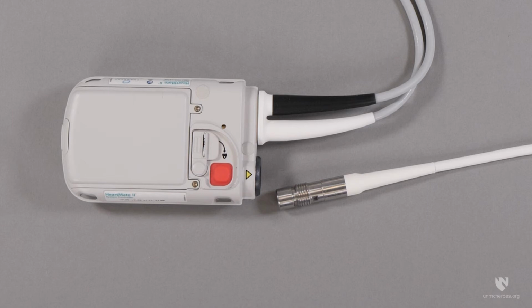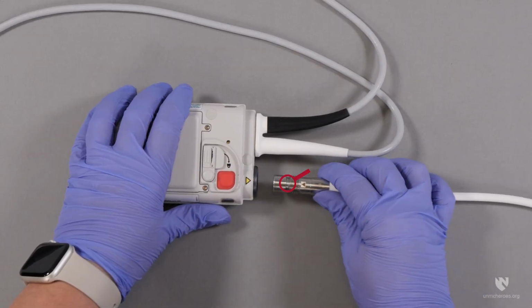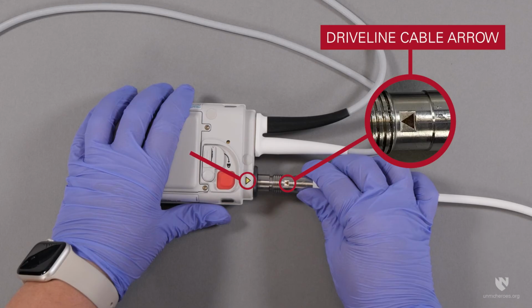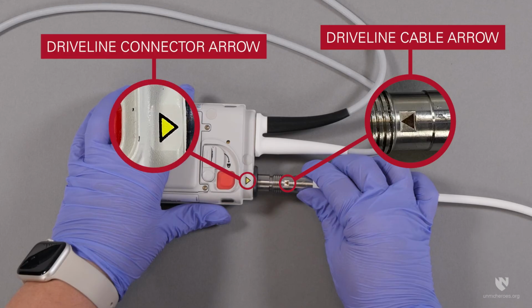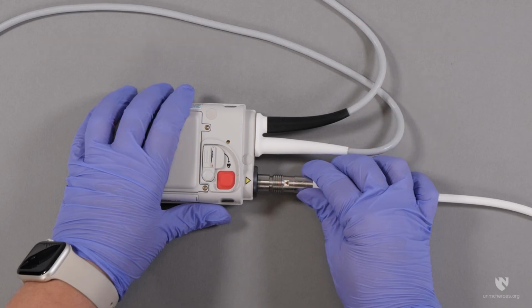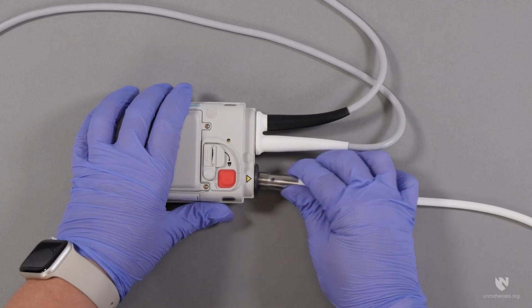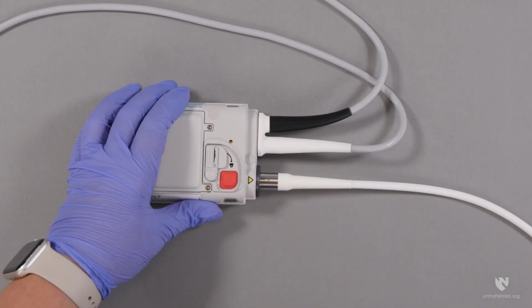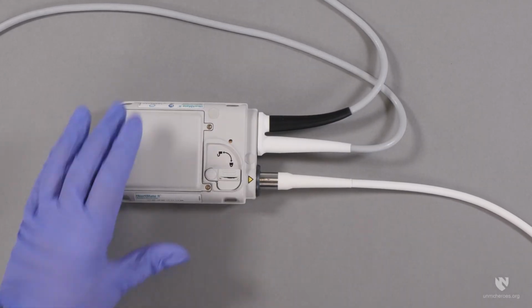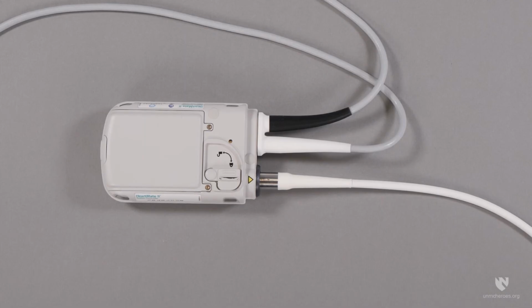If the driveline cable has become detached from the system controller and it is appropriate to reconnect it, you can reattach by aligning the driveline cable connector alignment arrow with the system controller driveline connector alignment arrow. Then insert the connector. When fully inserted, you will hear a click. Lastly, rotate the safety lock on the back of the system controller into the locked position.